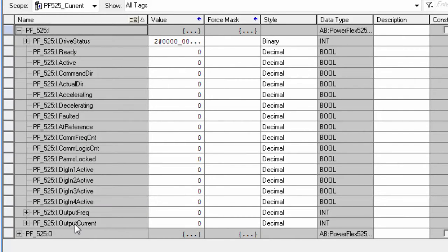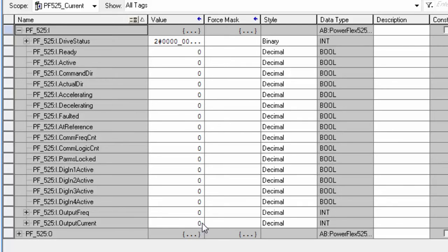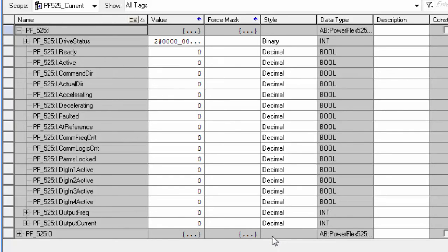Right here is where you would read your output current on the drive. So this will be displayed in tenths. So you'll want to take this and divide it by 100 and change it to a floating point. Then you can get 1.0, 0.99, whatever typical two horse or one horse motor would be running. Then you'll get your feedback from that drive depending upon load variables. But this is where you would read it from.